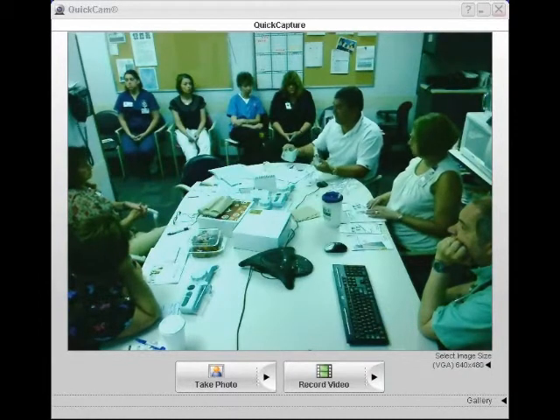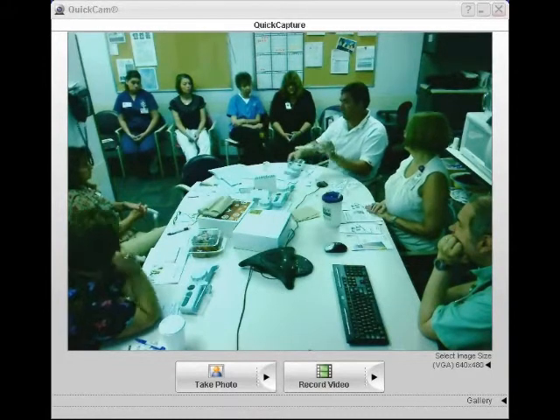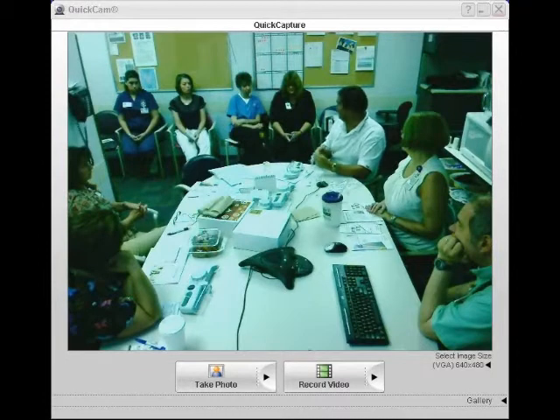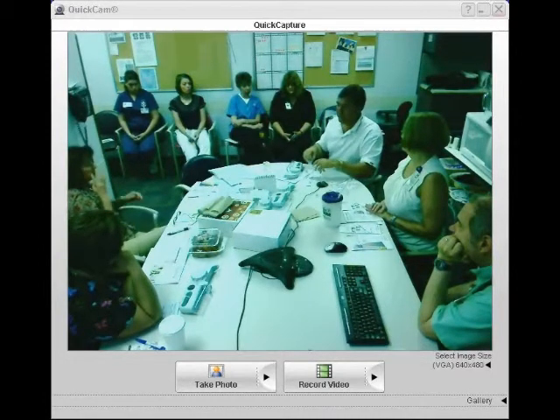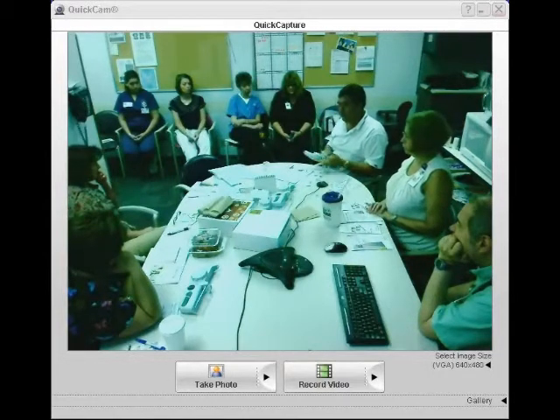They like that. Anyway, so we're going to load the syringe into the driver itself now. And this particular driver, there's only one way. I like to leave the numbers up on the top surface. It just makes it easier. You can tell how much you've infused and how much you haven't infused. But these wings lock into this particular pump one way or the other. So you're going to need a syringe that's like that.